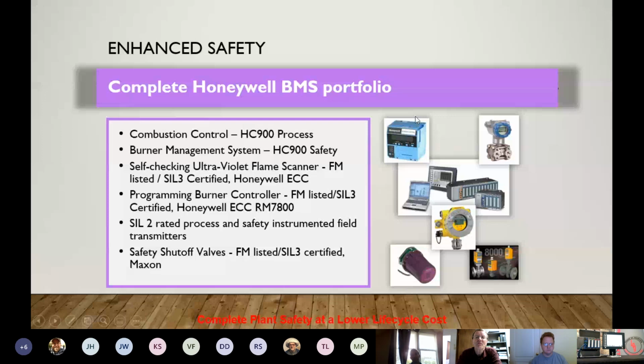So the last slide before we get into the operator interface and some of the programming real quick. Honeywell does have a full complement of products that can be tied together with the HC900 to put together a tight integrated control package, where you can be assured that you're providing a single source solution for your customer or the process out in your plant, where you have one source to go to help you with all these other items. The HC900 on the top left-hand side can be tied into the RM7800 with Modbus if you wanted to. So you can communicate 3-wire right from the display or a Modbus module on the top of the relay into the 232 or 485 port into the HC900.